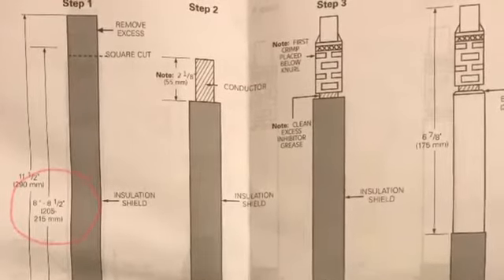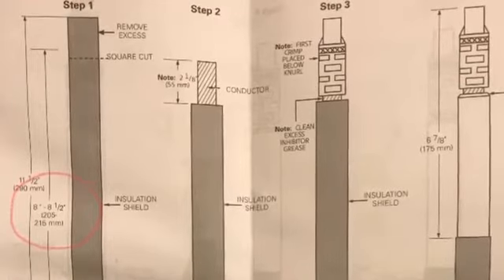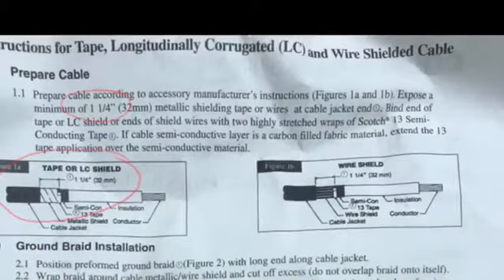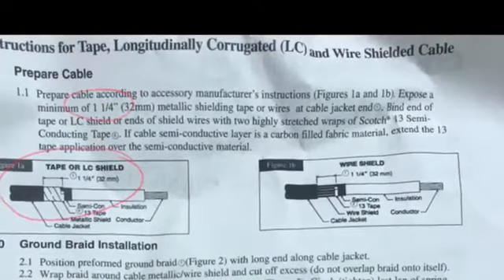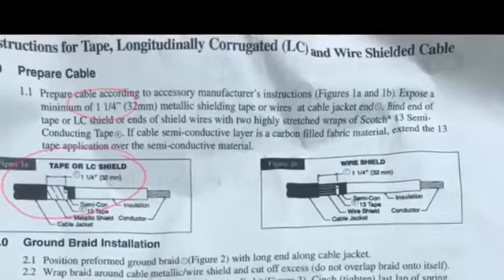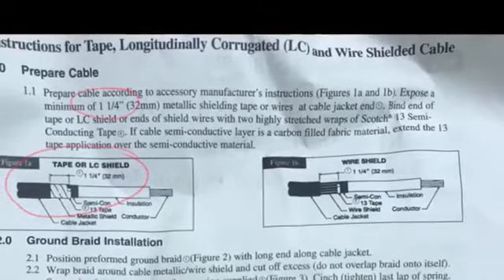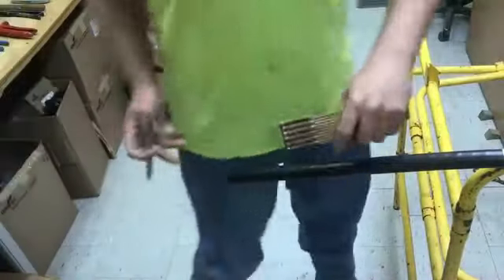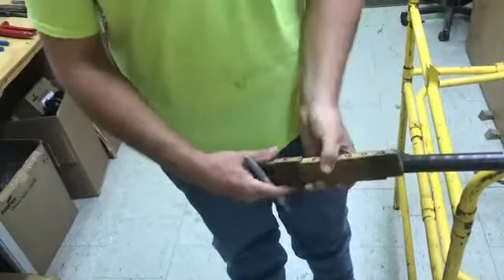which we would take, the 8.5 inches. Well, we have to compensate for our tape shield cable, so going to our SA2 instructions, it needs a minimum of 1 1/4 inches to make the connection to the ground braid. So we'd add the 1 1/4 inches to our 8.5 and come up with a 9 3/4 cutback. We'll go ahead and mark that on our cable and make our ring cut.